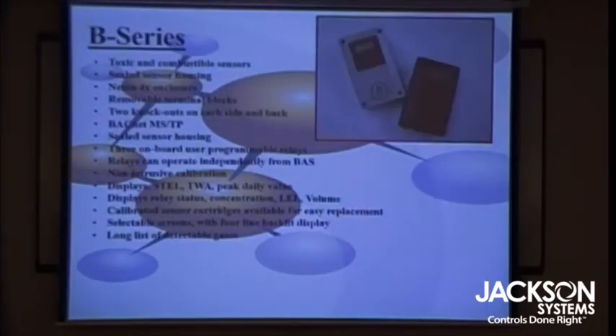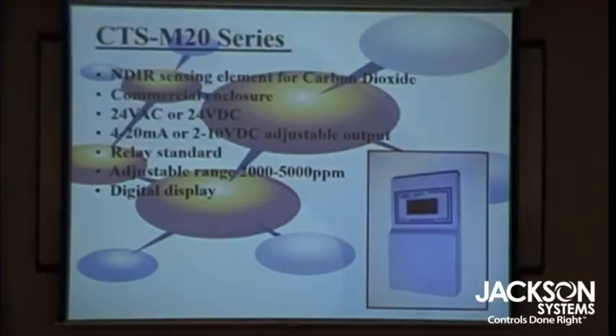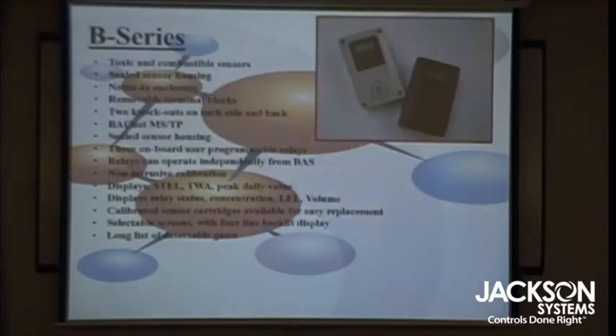And as I forgot to mention before, the B series and Q series, you can actually have in duct mount versions. So if you're doing NO2 or CO duct mounting, venting from a bus garage or something, basically what we do with a duct mount is that we place an adapter over the front cover of the unit. It screws on. You see the triangle of the 3 screws, and we have a couple of fittings with the pitot tube that goes into your duct.